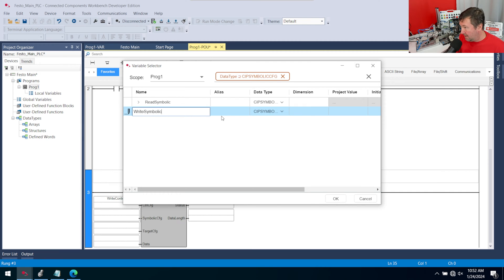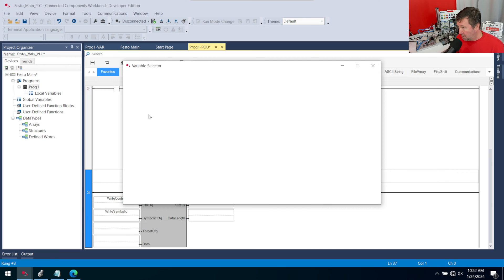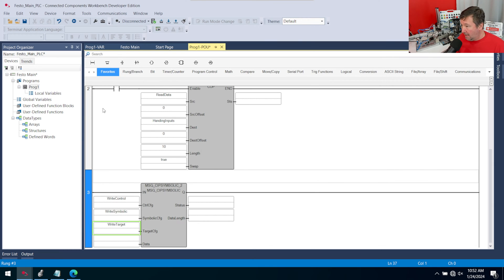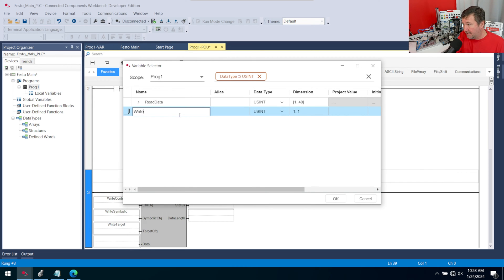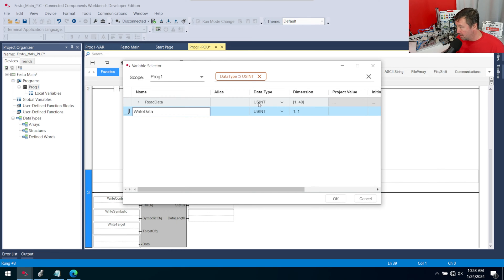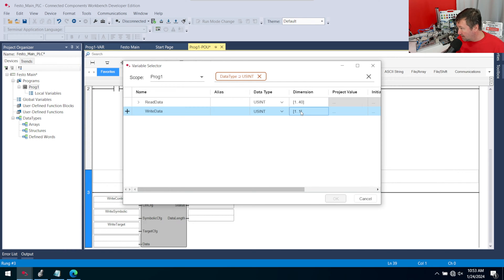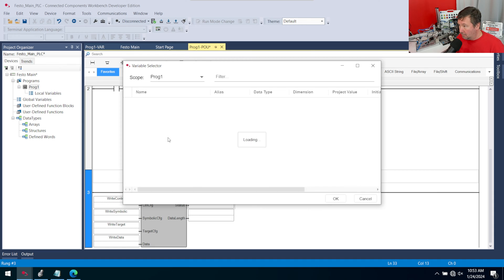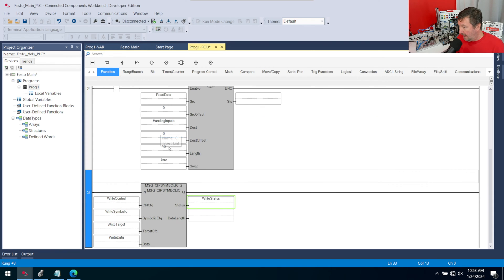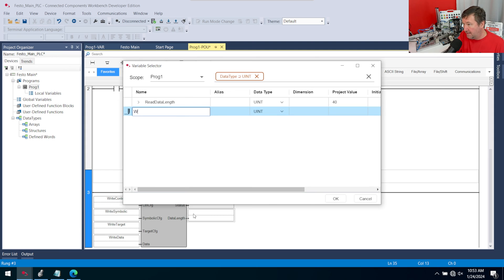Notice it already fills in the data types all the way down. Then our target config — I'll call this 'write target.' And we have our data — I'll call this 'write data.' Similarly to the read, since we are doing 10 double integers and these are small integers — small integers are 8-bit, double integers are 32-bit — we need whatever we're writing to times 4, which is why we have 40 here.